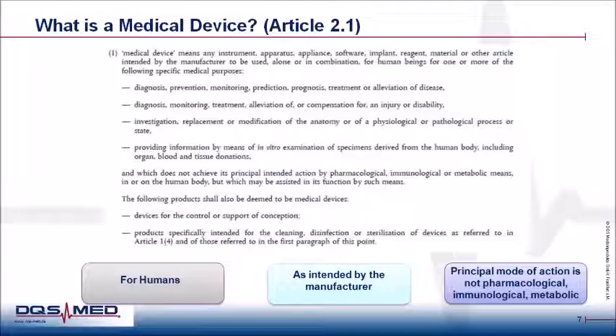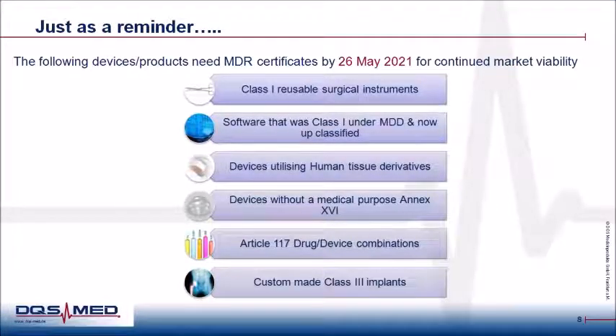A slight reminder, as you know, in addition to the products meeting the MDR's definition of medical devices, it must also be noted that the MDR even contains new items such as Class 1 reusable surgical instruments, drug-device combinations according to Article 117, devices utilizing human tissue derivatives, or software that was currently classified as Class 1 and has now been upclassified depending on the intended use as either Class 2A or 2B. And most importantly, the devices according to Annex 16, that while being aesthetic or non-medical, have no medical purpose, but still must comply with the MDR specifications, and that too after 26th May 2021, in order for them to be market viable.